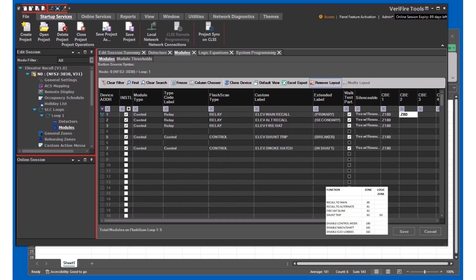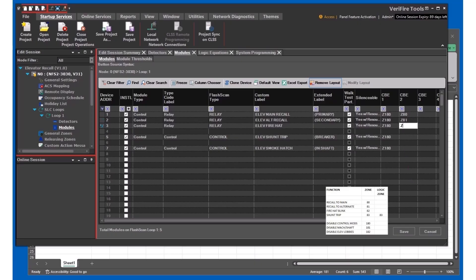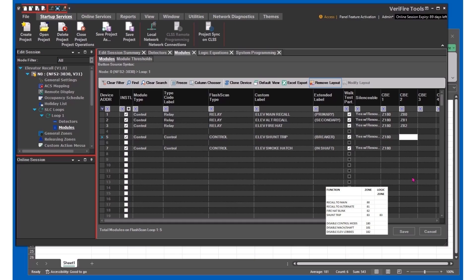Remember, main is zone 80, alternate 81, blinking hat 82, shunt trip. Now remember, we're going to do a time delay, so we're going to use a logic zone for that. That's going to be ZL 83, and then our hatch is zone 84.